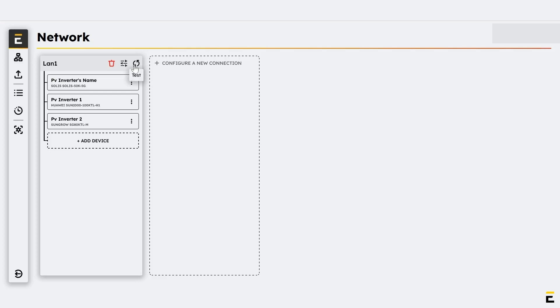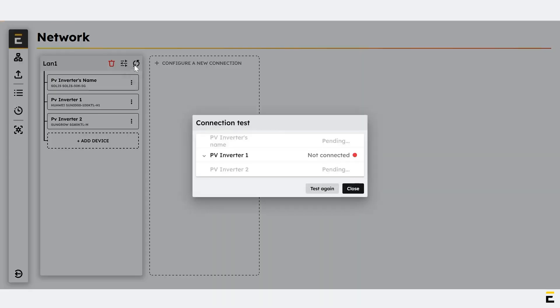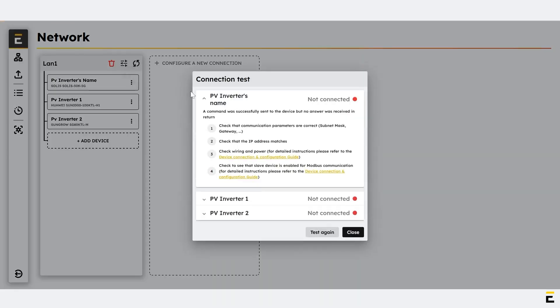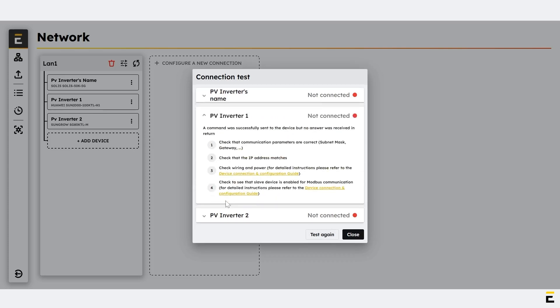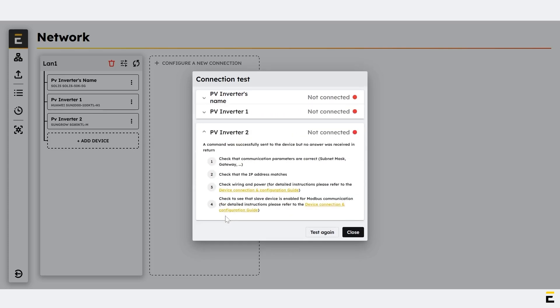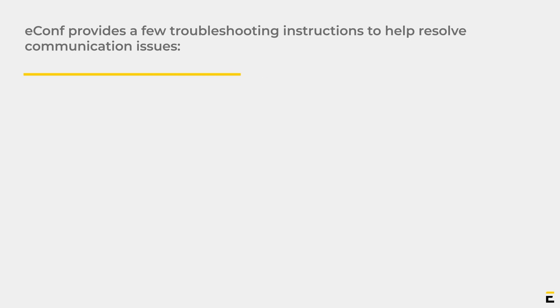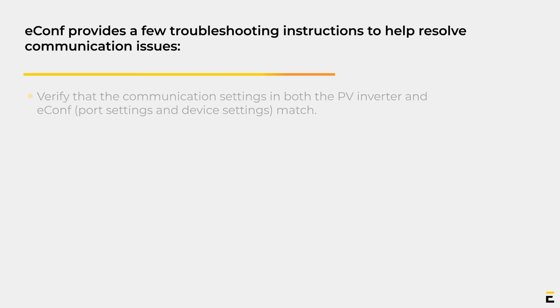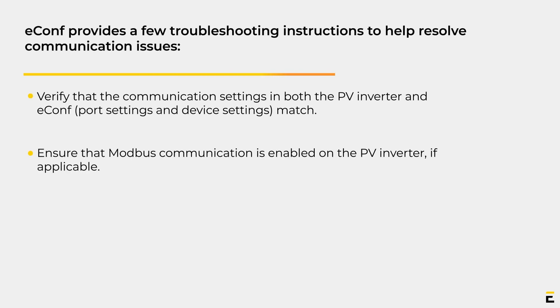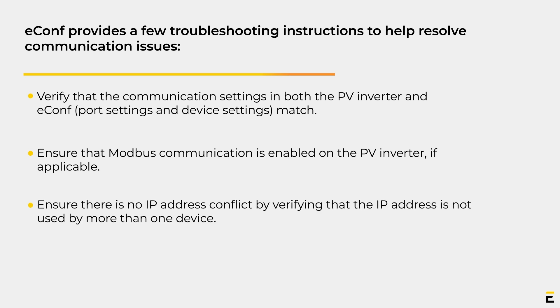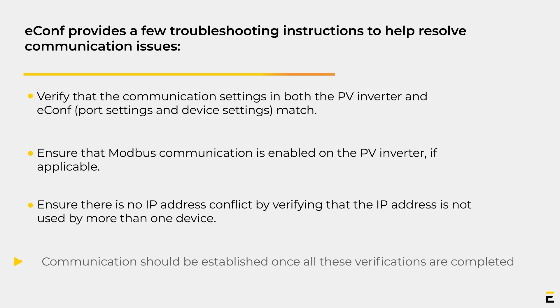Another way to test all devices connected to the same port in a daisy chain is by clicking the refresh icon next to the configured port LAN 1. This will display the status of those devices, and you can expand the window by clicking on the device name. eConf provides troubleshooting instructions to help resolve communication issues. Once all these steps are completed, communication should be established.